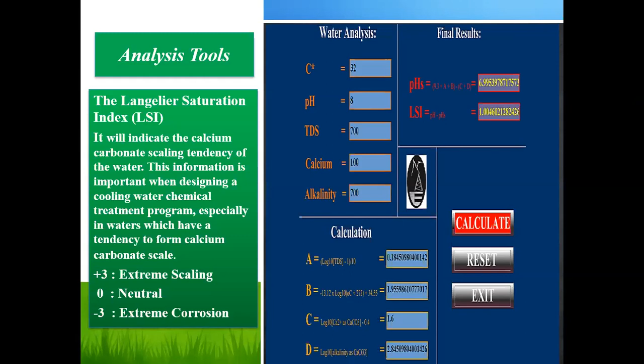So if you have something in positive figures, it's towards scaling. Something in negative figures, you will have towards corrosion. You can see a rough picture of that sheet. Here the calculation formula is also given, and the LSI is 1. 1 is normally fine. It will not have that much scaling, because you cannot afford corrosion in your system. A bit of scaling is obviously a good thing, but you can reduce that to 0.8 or 0.7 or whatever.